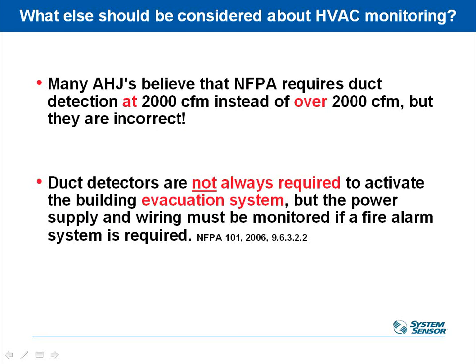So with that being said, yeah, if it's 2,000 CFM, you don't have to do it, but you're probably still going to get flagged by the inspector and have to deal with that. So if you're going to do a 5-ton unit, either provide a duct smoke detector or set it up so it only does 1,950 CFM or something like that.